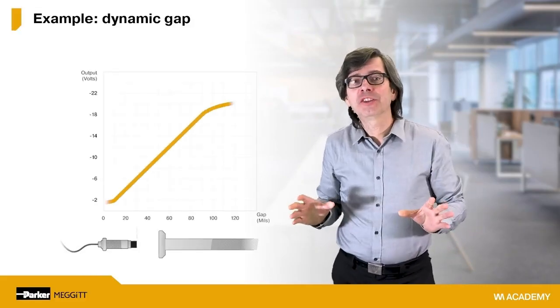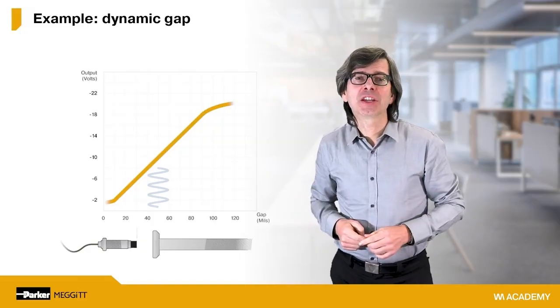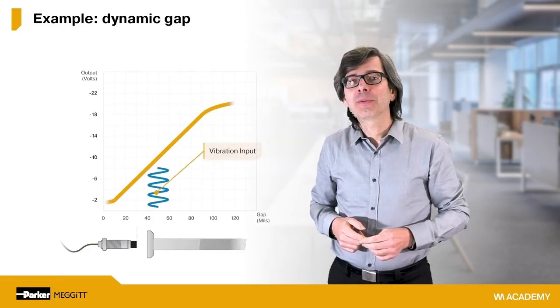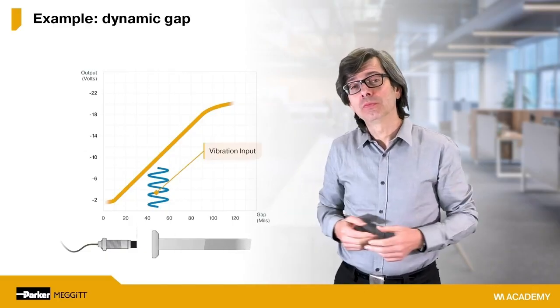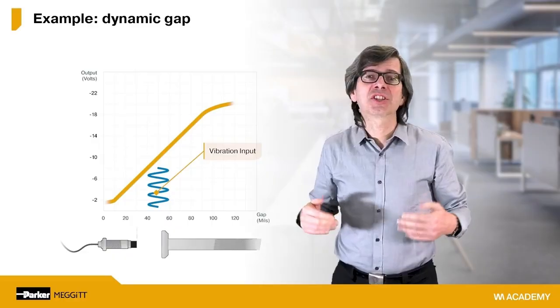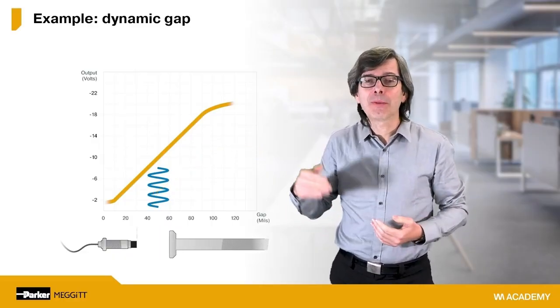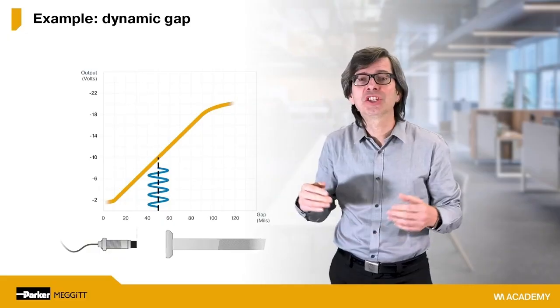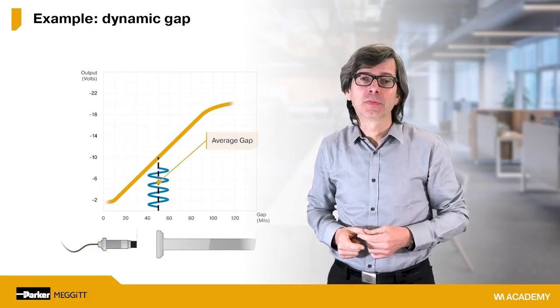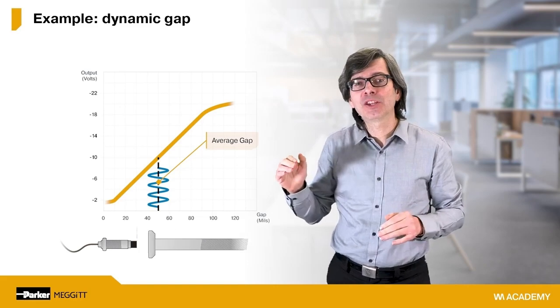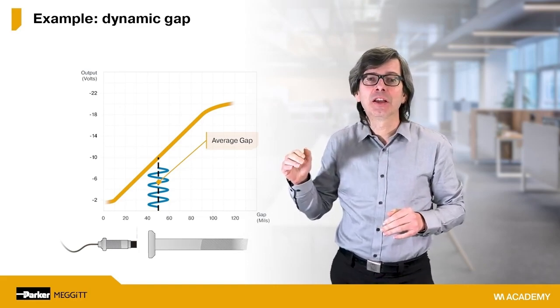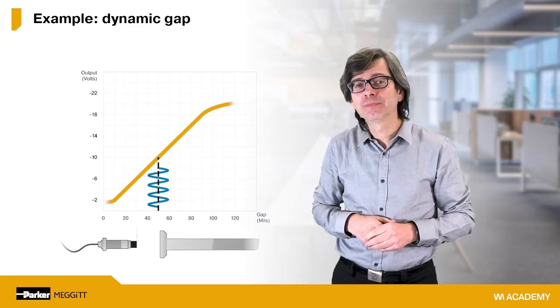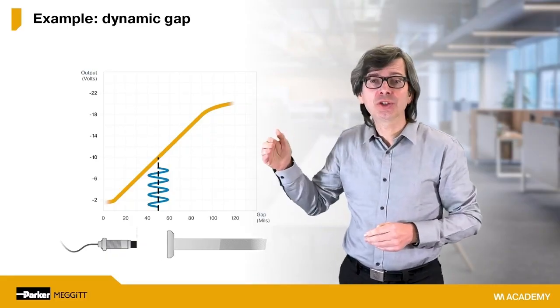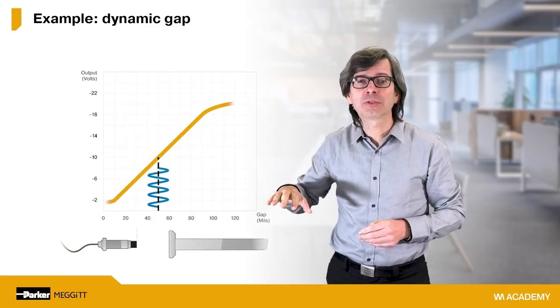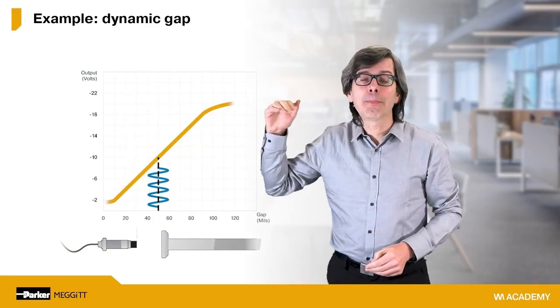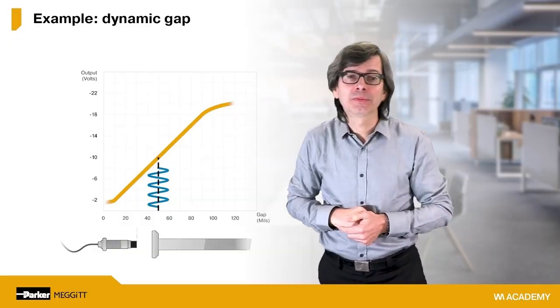Let's now illustrate the effect of a dynamically changing gap by introducing the vibration sinusoid in blue. This represents a shaft vibrating sinusoidally about some center position, which is its average gap. In this example, the amplitude of the vibration is 20 mils, as can be seen by observing the grid lines on the graph. The sinusoidal oscillation goes as low as 40 mils of gap and then up to a maximum of 60 mils of gap, and then back again.